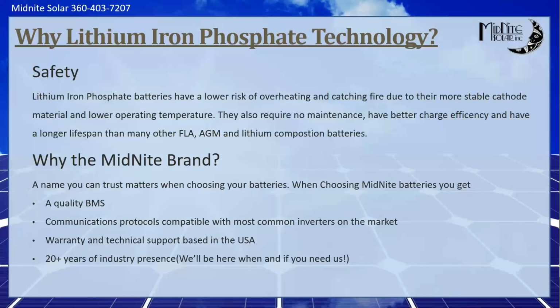Lithium scares me, I'm afraid of lithium fires, but I've seen a lot of lead acid fires. Personally, I've seen people install multiple strings of lead acid batteries where one has an internal short and the other is getting hit by it. Stuff catches on fire. I've seen cold flow on the lead terminals, loose connections, things arcing and burning. We were in a fire investigation on a residence that had a battery fire in a crawl space with some of our equipment in the system.